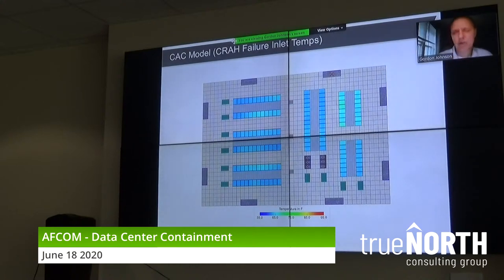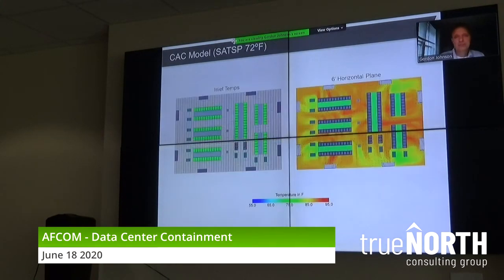If you look down around that failed CRAH unit, because of the way that CRAHs are spaced, I no longer have a 1 or 2 degree delta. It went up 5-6 degrees until I fixed that CRAH unit, but so what? It's running at 68, 67 instead of 62. I still have a very nice, cold, consistent data center to operate in.